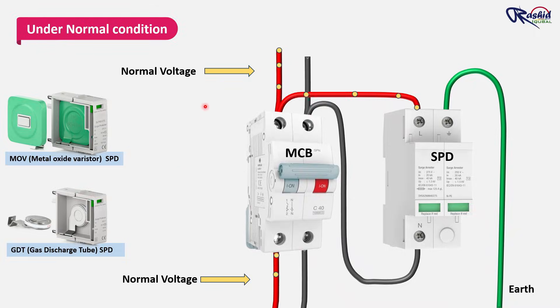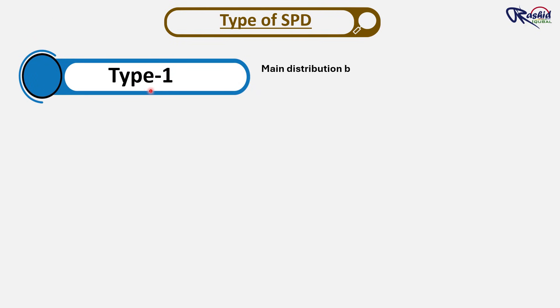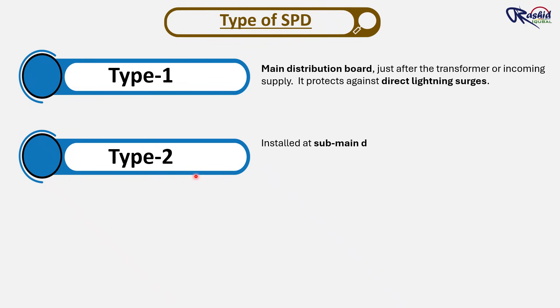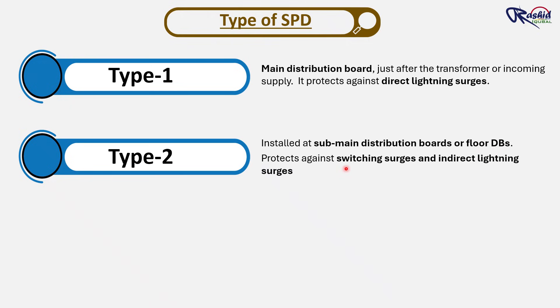Now let's learn about the different types of SPDs. There are mainly three types as per international standards. Type 1 SPD is installed at the main distribution board, just after the transformer or incoming supply. It protects against direct lightning surges and is a heavy-duty SPD, often using spark gap technology. Type 2 SPD is installed at the sub-main distribution board (SMDB) or floor DBs. It protects against switching surges and indirect lightning surges, and is the most common SPD used in residential and commercial buildings.